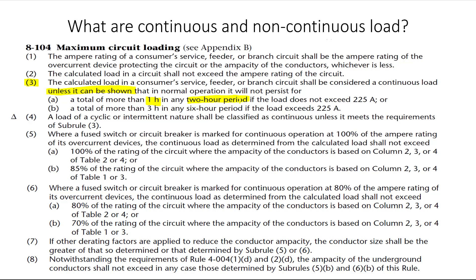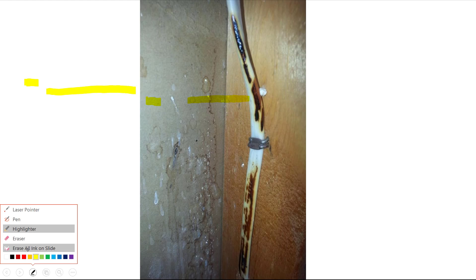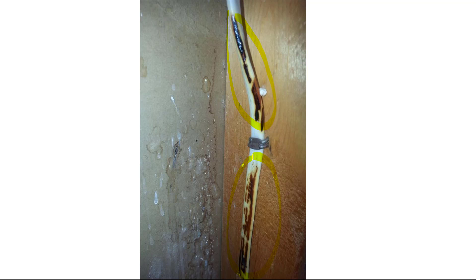Why is it important to correctly size your wire and circuit breaker for a specific load? Every load causes a value of current to flow in the circuit conductors. As the electrons travel, heat is created due to the resistance in the conductors. If the conductor is incorrectly sized, the heat buildup due to current flow will cause the insulation around the conductors to melt and break down. This can quickly lead to a fire within the walls of the building. Here we see an example of a conductor exposed to too much current, with the insulation broken down due to excessive heat.